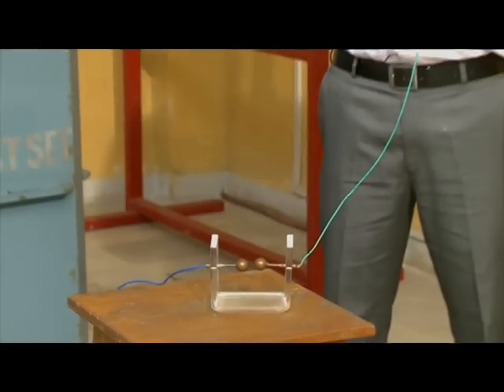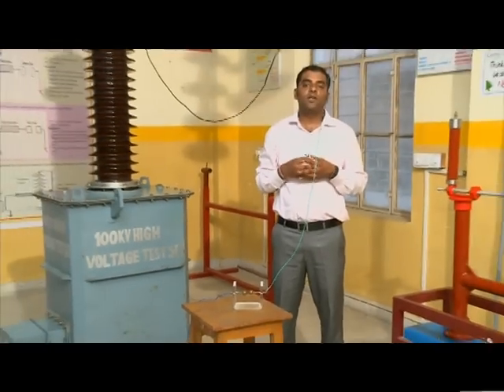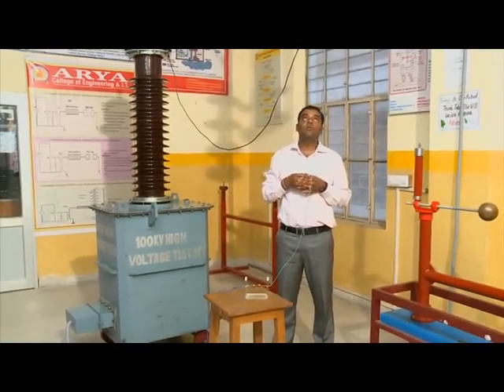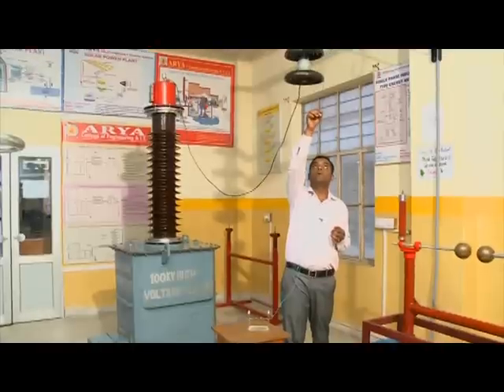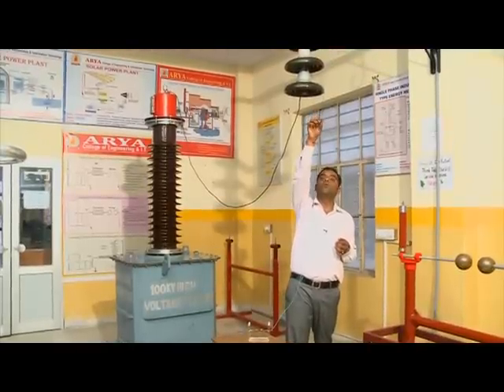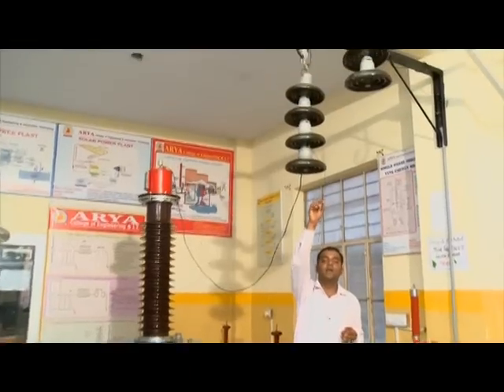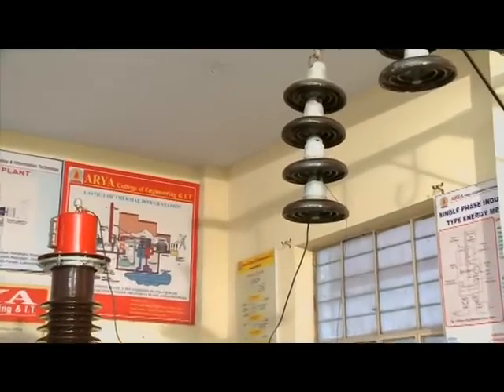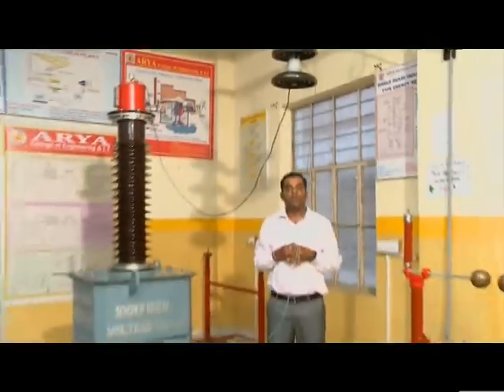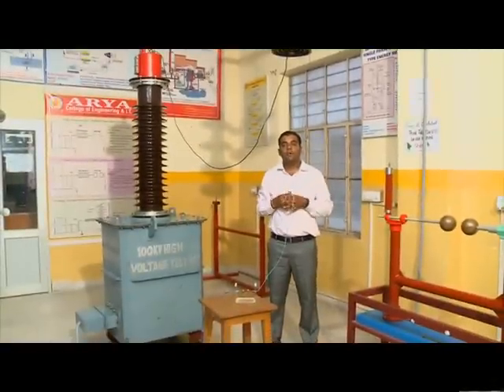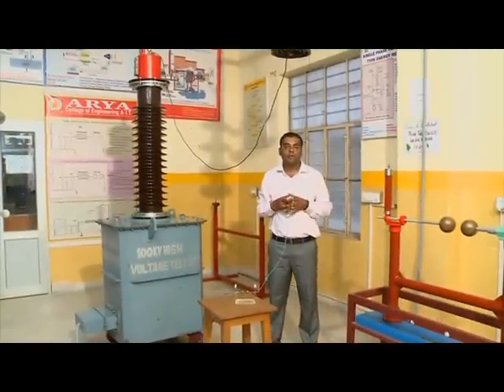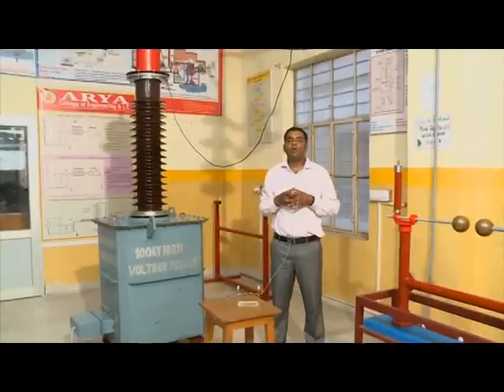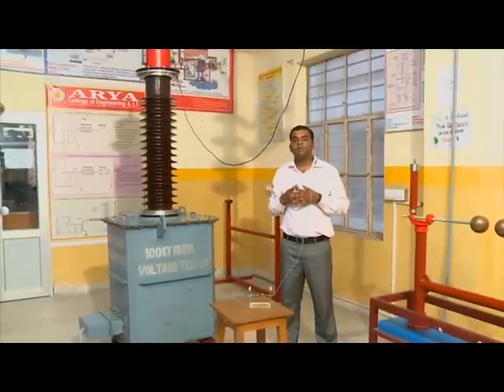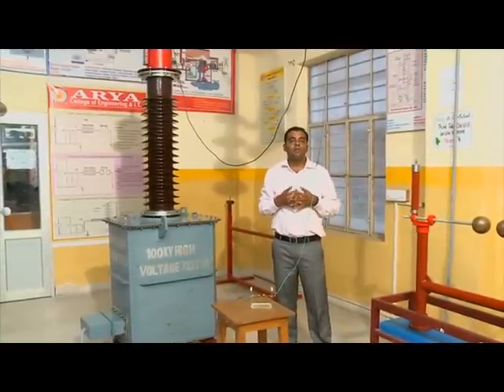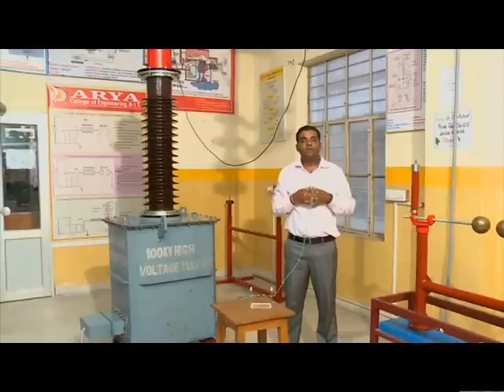For finding the value of spark over voltage for the complete string, we have to connect this wire with the fourth unit of that insulator string and find out the value of voltage when the breakdown of air will occur. That value of voltage at which the breakdown occurs is called the spark over voltage of the insulator string. Then we will substitute these two values in the formula.